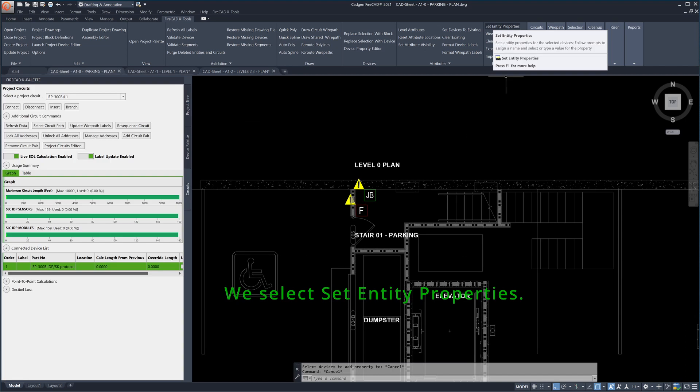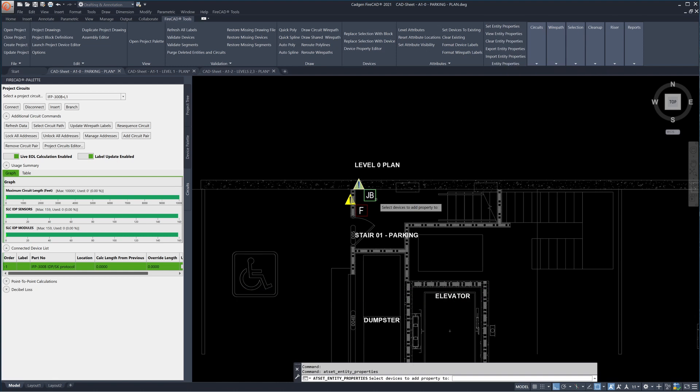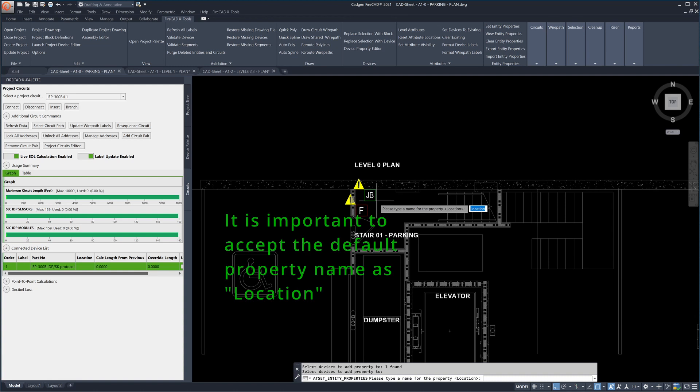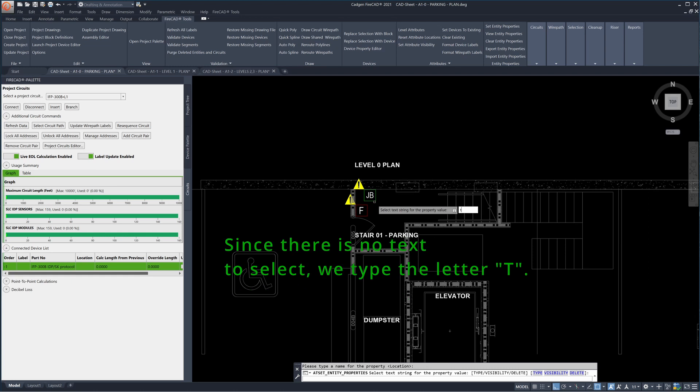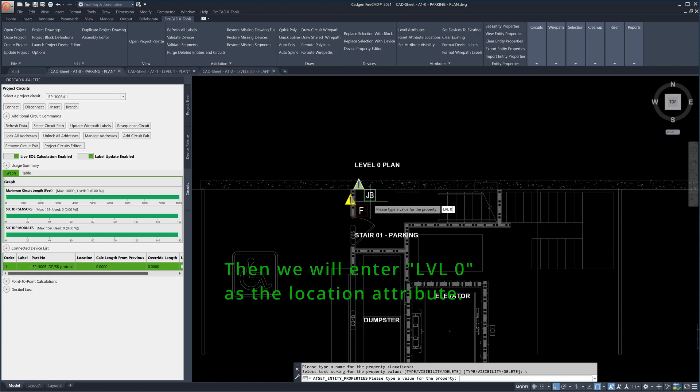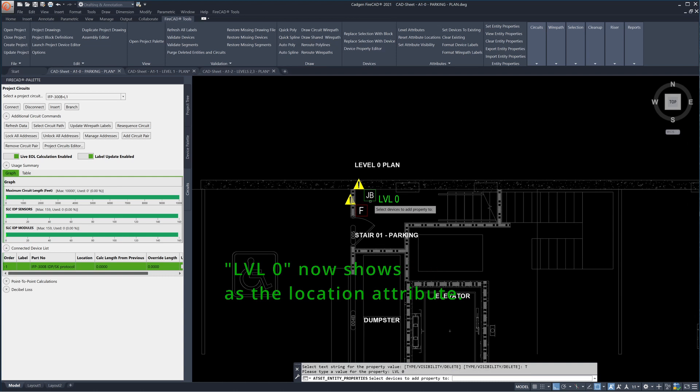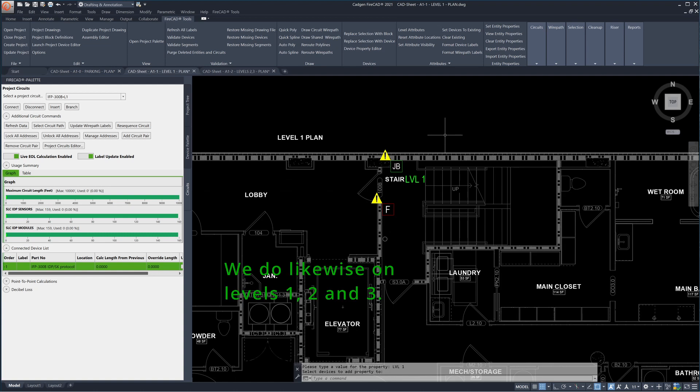A very important step is to set the entity properties of the junction boxes. These junction boxes will help us set the structure of the riser's backbone. It is important to accept the default property name as location. We are asked to select the text to use as the attribute value. Since there is no text to select, we type the letter T. Then we will enter level 0 as the location attribute. Level 0 now shows as the location attribute. We do likewise on levels 1, 2 and 3.